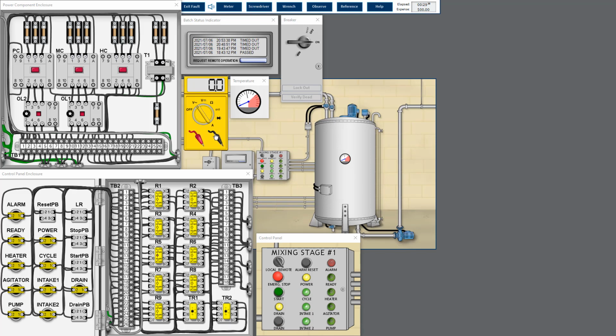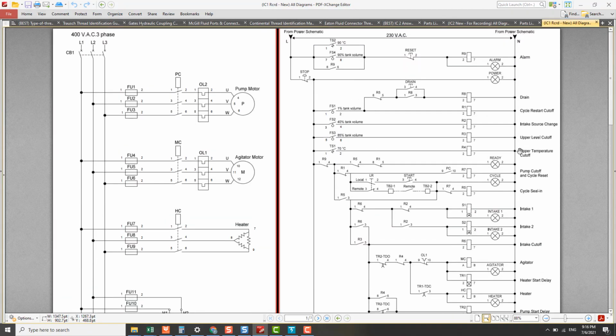Now we check the transformer voltage. We set the meter to AC voltage mode and check the transformer voltage. It looks normal, at 230 volt. Now we confirm the transformer has no issue. The second thing we need to check is the common neutral, suspected of having a very loose connection or open circuit, or a slightly loose connection or a load with slightly high resistance. As we know, the common neutral line is just a wire with the lowest resistance, so the voltage at the common neutral line must be 0.